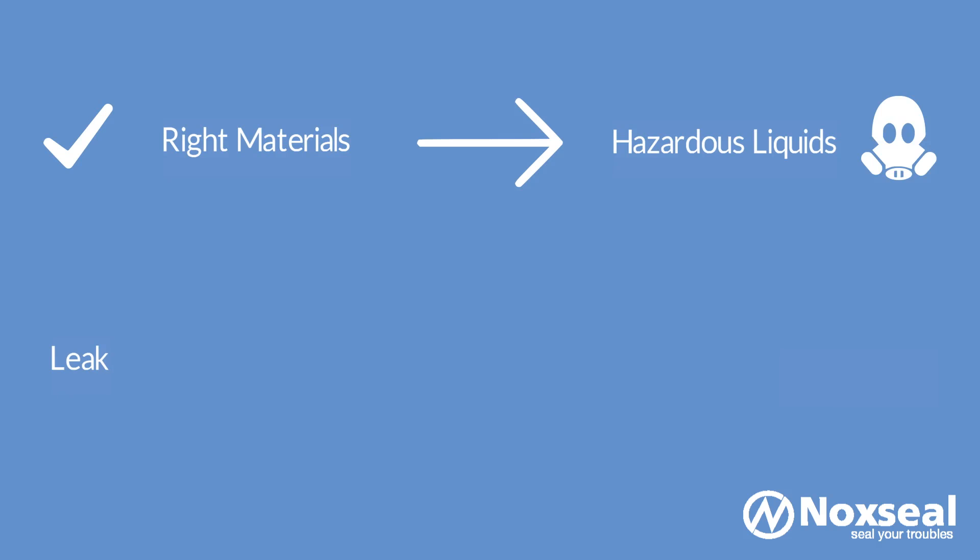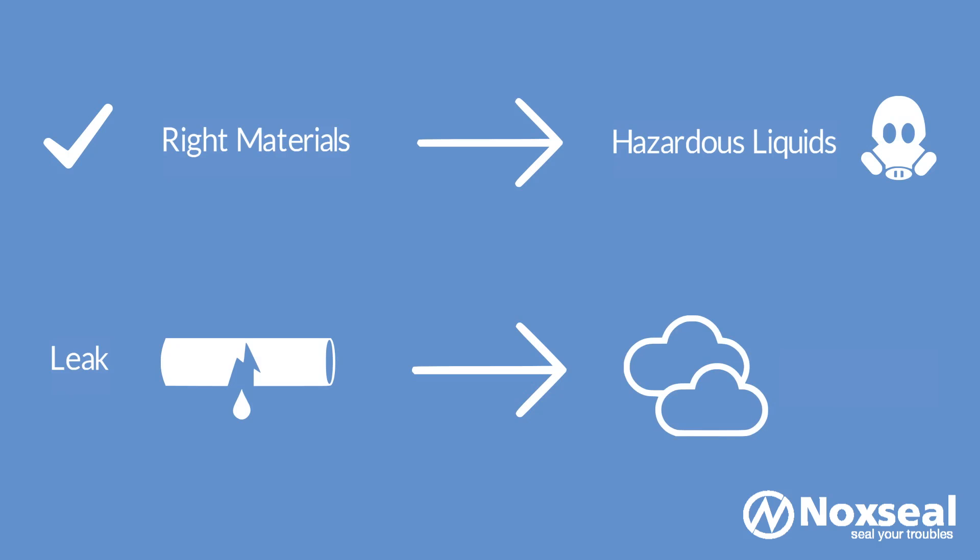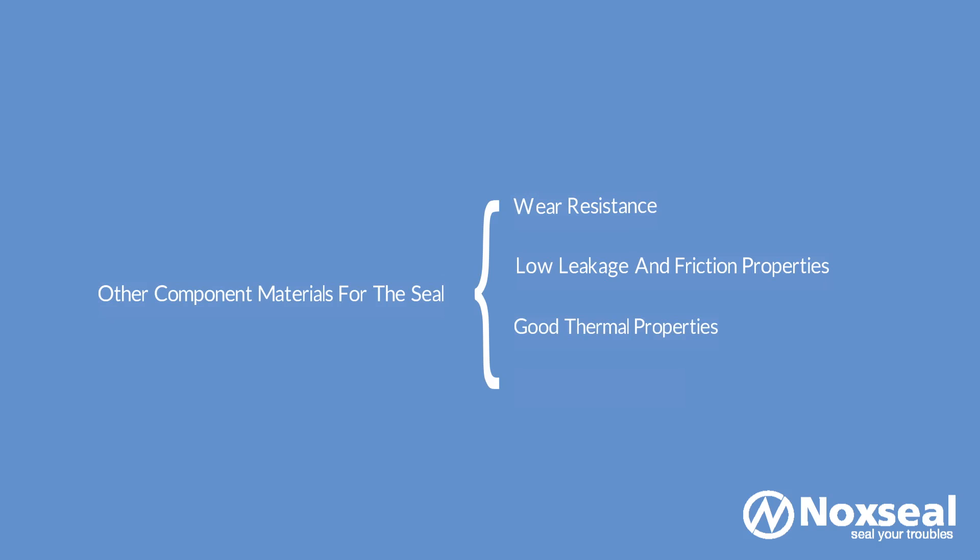Choosing the right materials for the hazardous liquids is very important, otherwise there will be chances of material failure and the liquid will leak into the atmosphere, which can be dangerous to the people handling the pump and also to the atmosphere. When selecting the face and other component materials for the seal, consider the following material characteristics: wear resistance, low leakage and friction properties, good thermal properties, corrosion resistant.